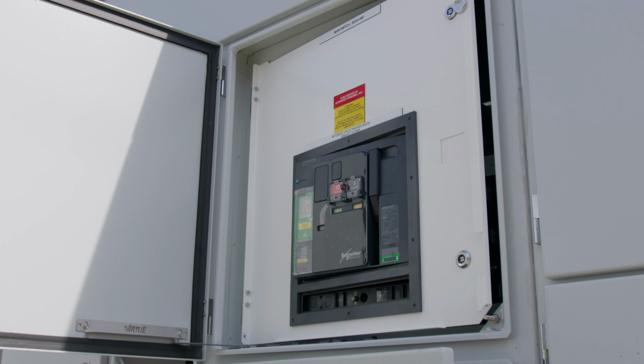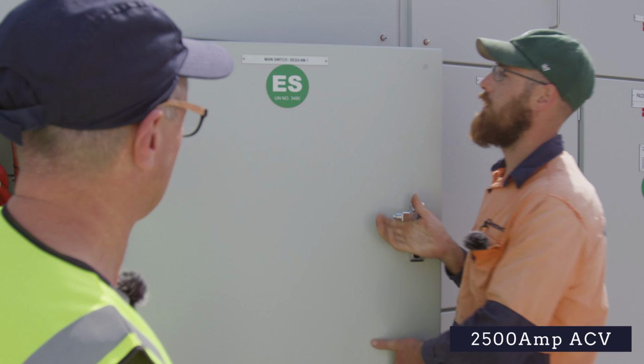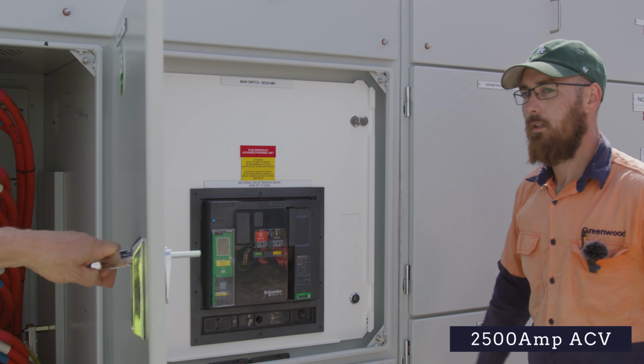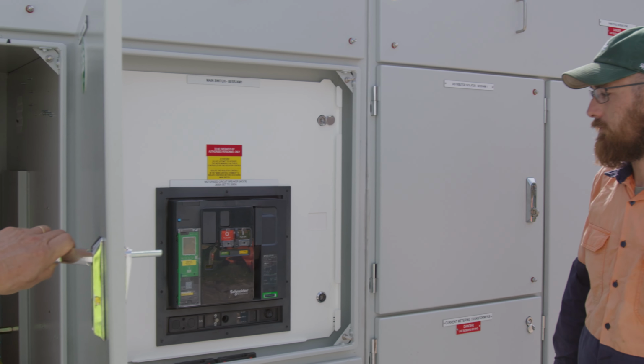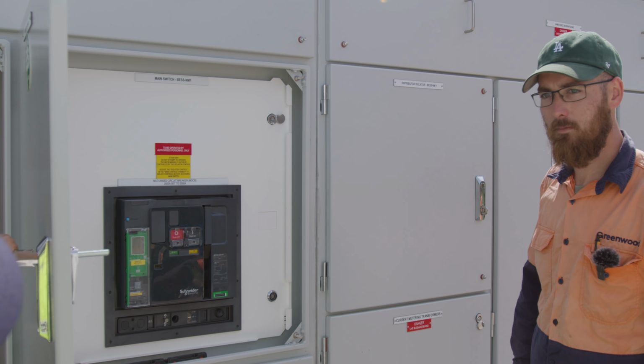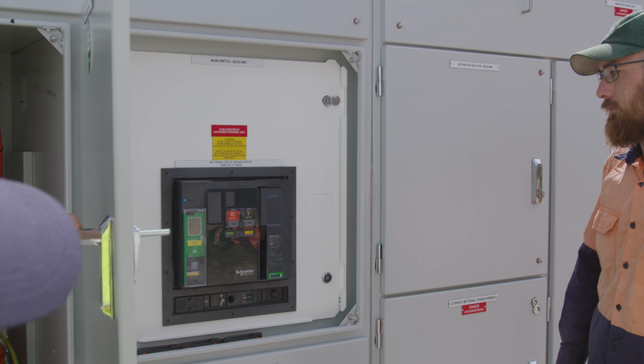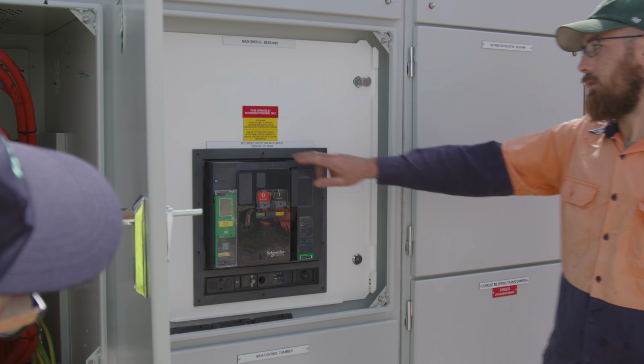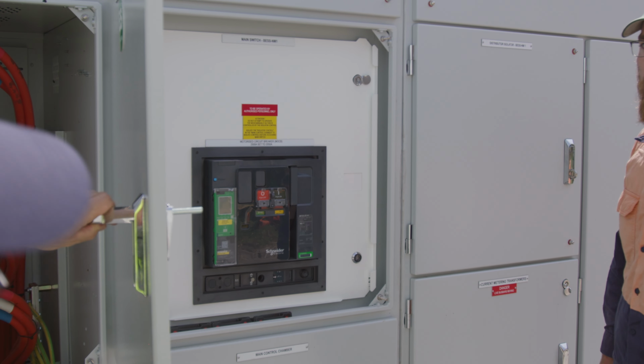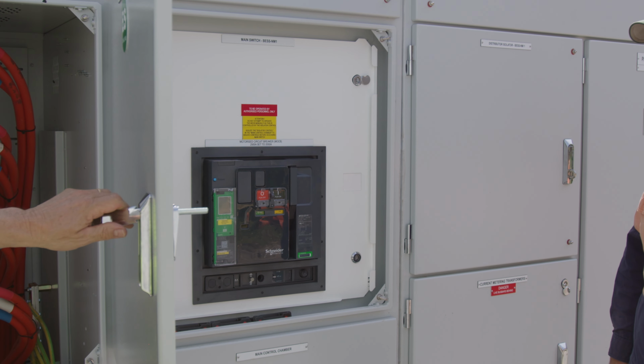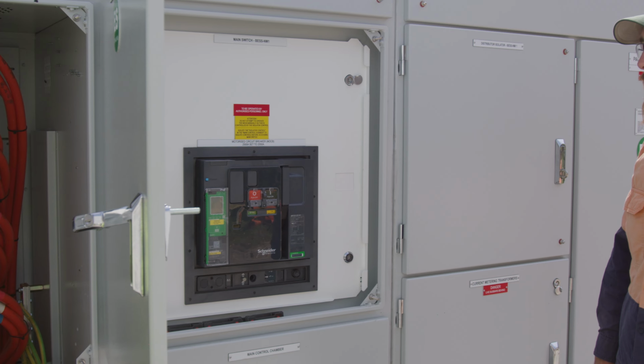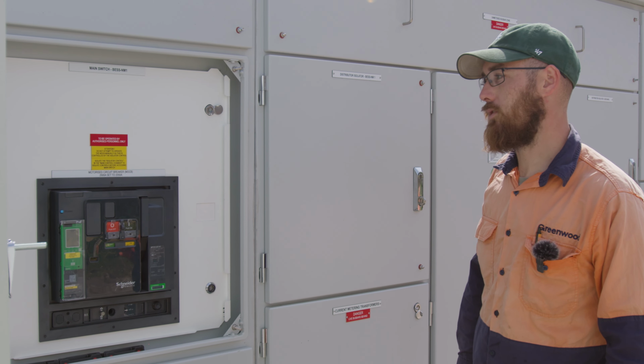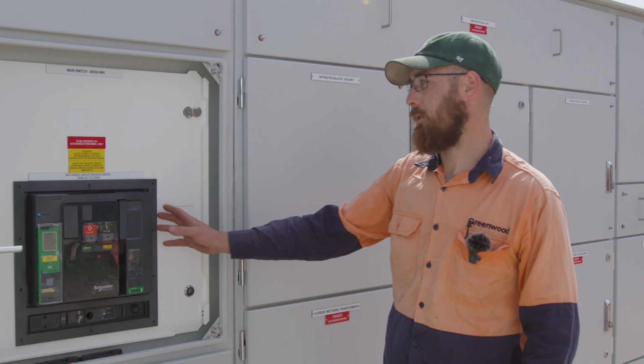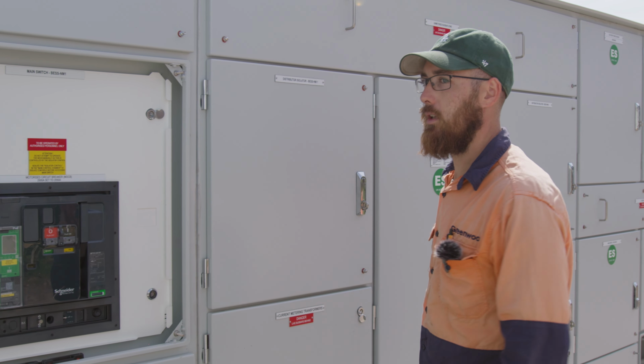Now the main switch. This is the main switch for this NMI. This is a 2,500 amp ACB. So we're talking a very substantial circuit breaker there. 2,500 amps set to 2,050 amp. Yeah, okay, that's very precise. Very precise. These breakers are very precise, and they have the ability to be controlled remotely. So this will also be connected back into the site controller.